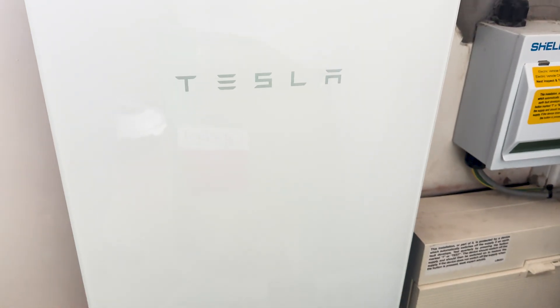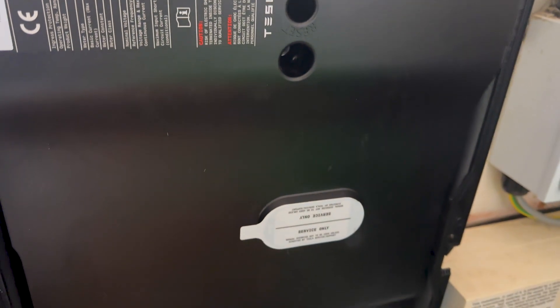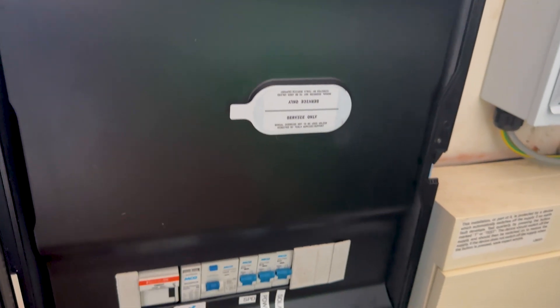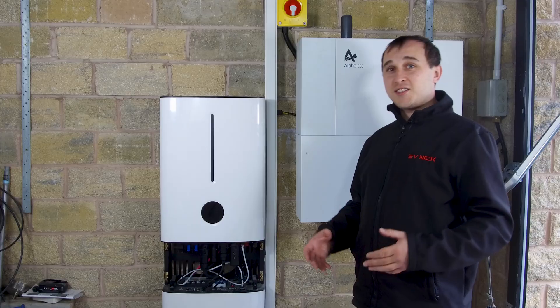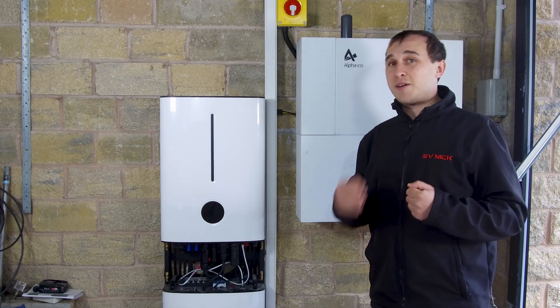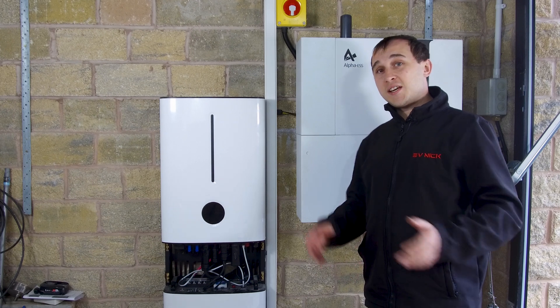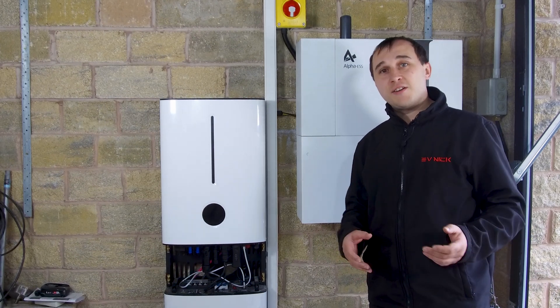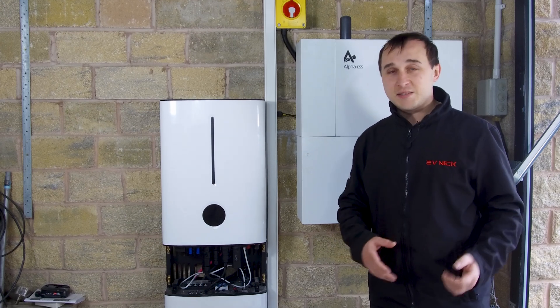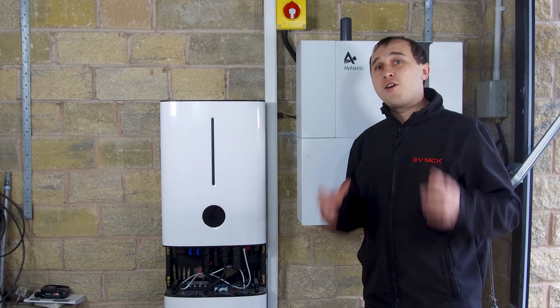Some systems like Tesla have a gateway which will automatically switch power during a power cut. However, you can't run really high-power devices on this — there's still a limit to what the battery can do. It's also worth noting that all systems, including these and the Tesla Powerwall, will require you to change your earthing arrangements. Depending on your earthing system, that might mean groundwork for putting in a ground mat or earth spikes all around your house.